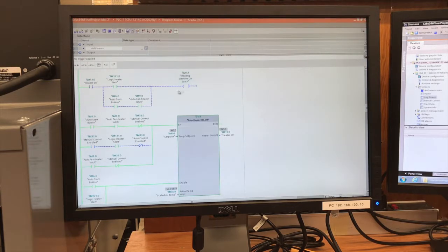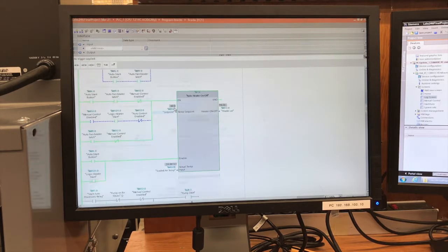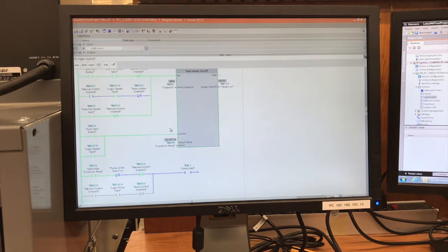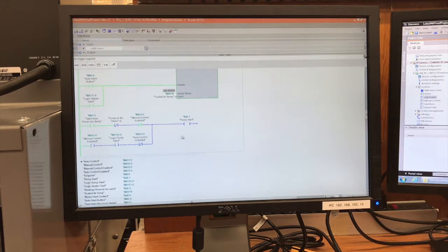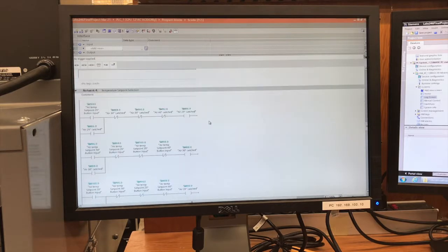You can also see that this block is turned off and on by the auto manual settings. Currently this block states false, the auto heater on and off block states false, so it actually turns off the heater. Down here is just another one for the pump, so this ladder logic will determine whether the pump runs or not, which is on a cycle for 70 seconds, so once every 70 seconds the pump will turn on for 10 seconds.